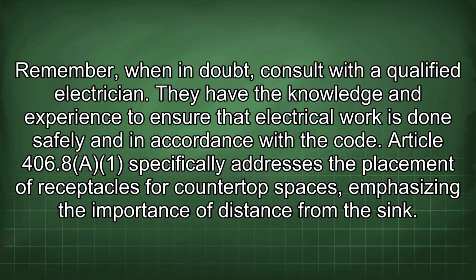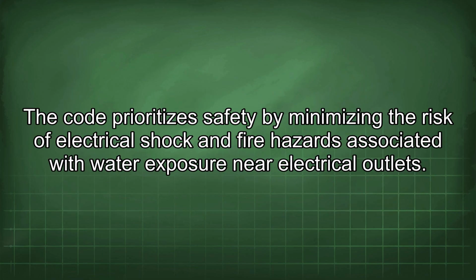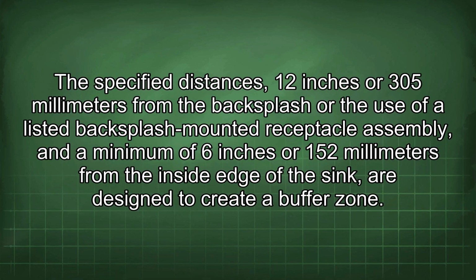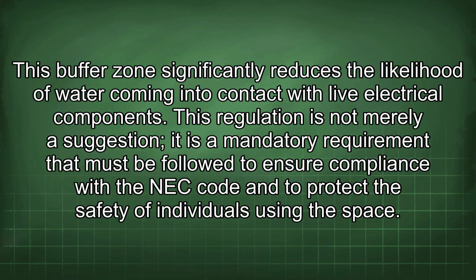Article 406.8a specifically addresses the placement of receptacles for countertop spaces, emphasizing the importance of distance from the sink. The code prioritizes safety by minimizing the risk of electrical shock and fire hazards associated with water exposure near electrical outlets. The specified distances, 12 inches or 305 mm from the backsplash, or the use of a listed backsplash-mounted receptacle assembly, and a minimum of 6 inches or 152 mm from the inside edge of the sink, are designed to create a buffer zone. This buffer zone significantly reduces the likelihood of water coming into contact with live electrical components.